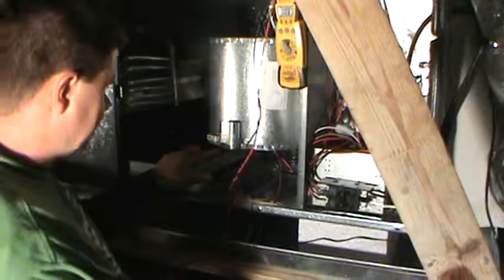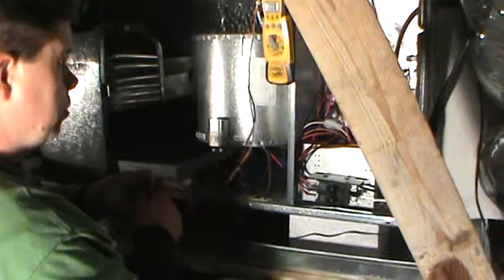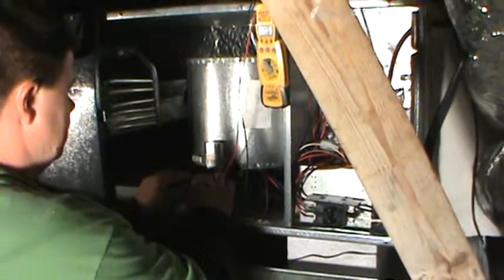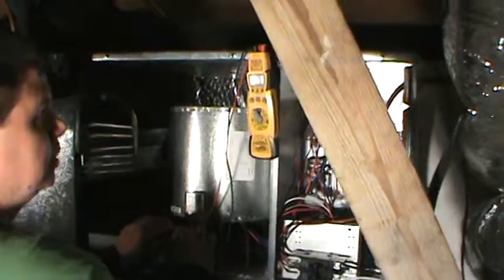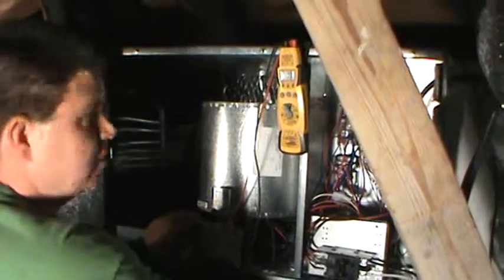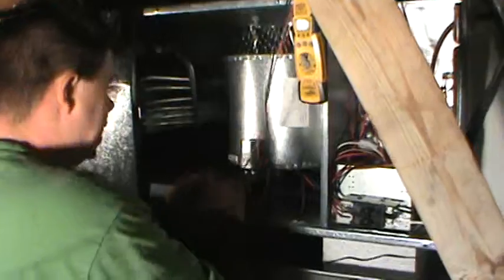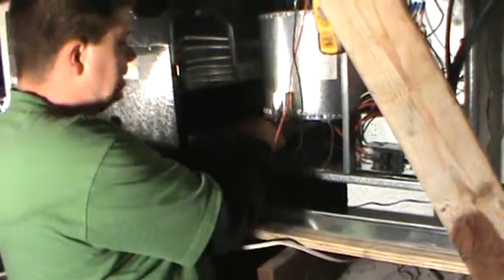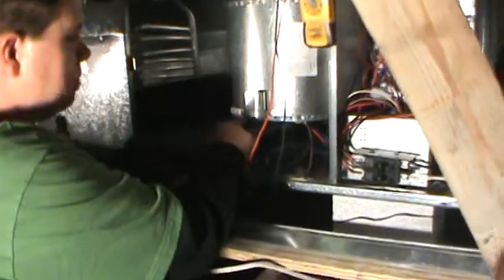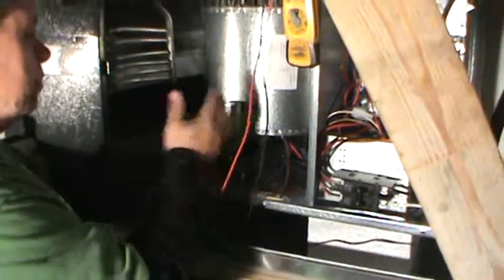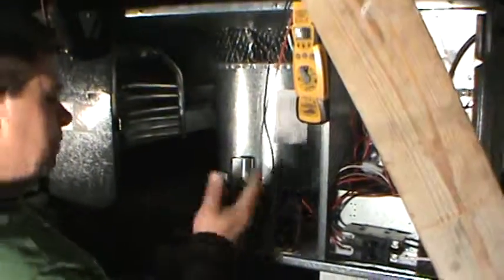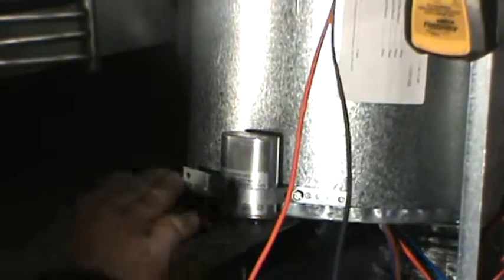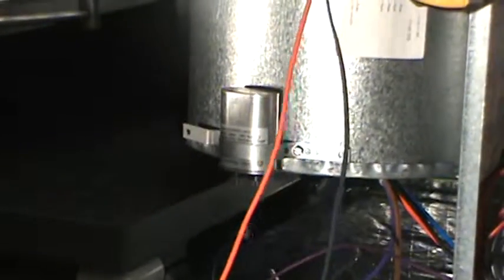This one is a 10 microfarad capacitor, so you just go between both leads, check, and there we have our 10.1 microfarads. Now everyone's a little bit different, but it'll say 10 microfarads, and it has a plus or minus, and this one's 5%. Some of them are 10%. So if you're checking it, and as long as it's within that range, that 5 or 10% that it calls for, then it's good.